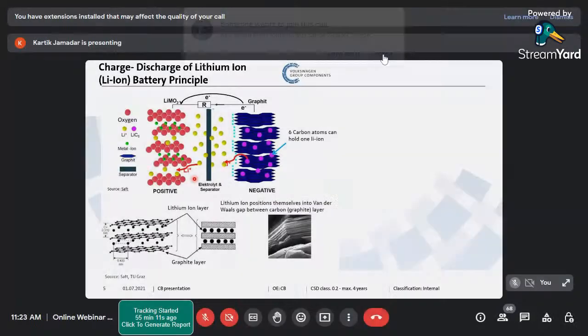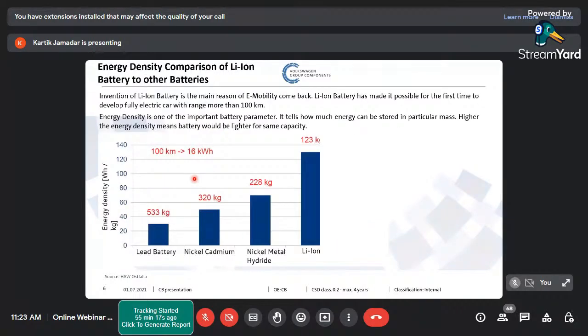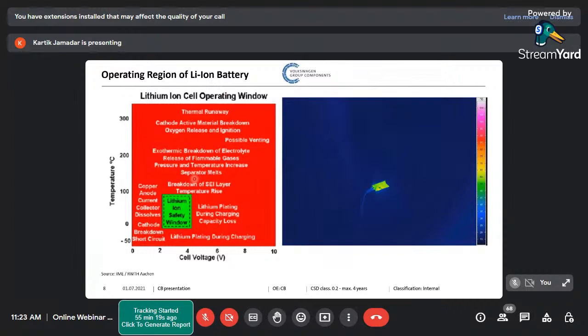Who is controlling that? You don't have to worry about it. There is a battery management system, which we call in short BMS, and that basically controls the voltage range. If one battery has reached that limit, immediately that battery will be discontinued or disconnected, and this can be done by passive BMS or active BMS, and that way the battery will be controlled within that zone. It is very important that we respect this voltage zone.